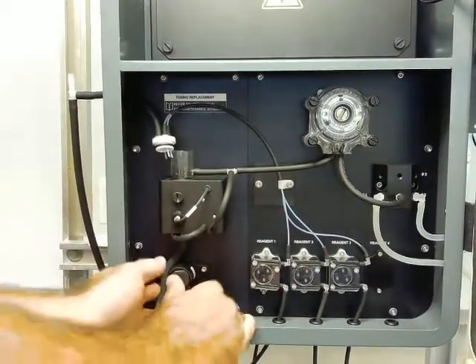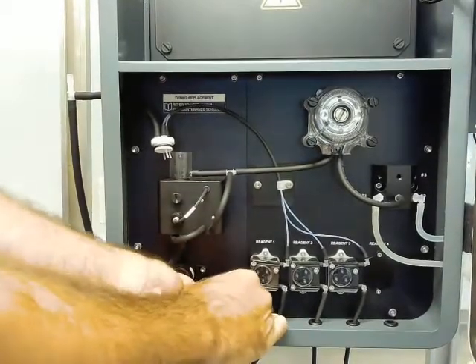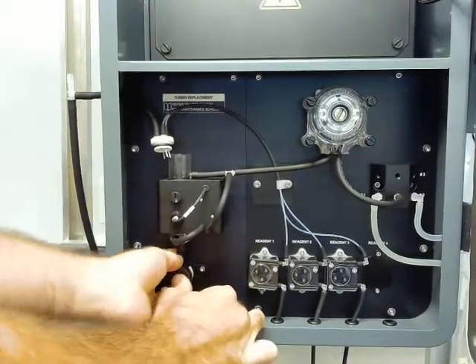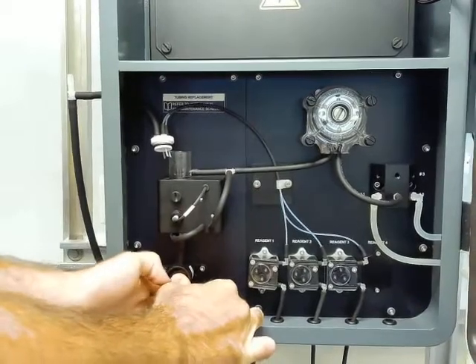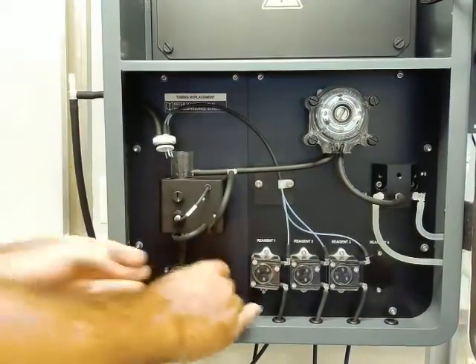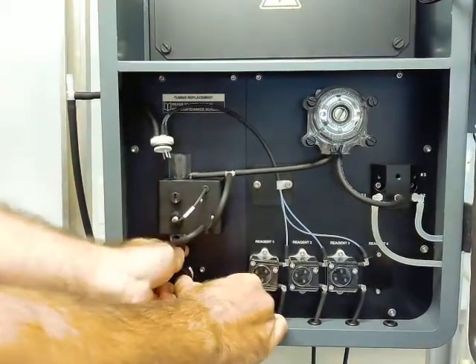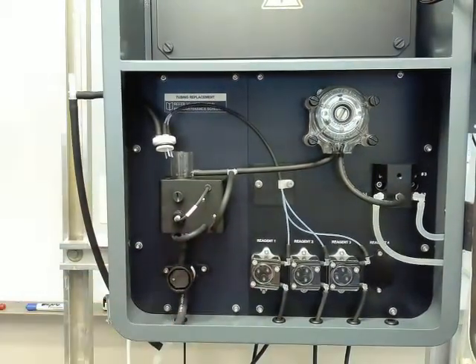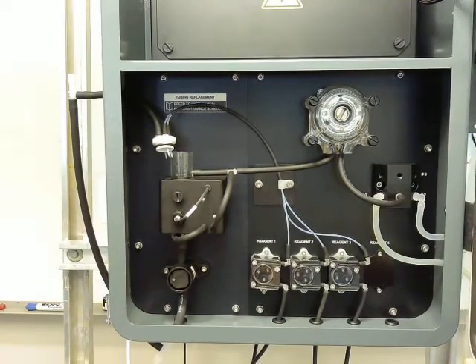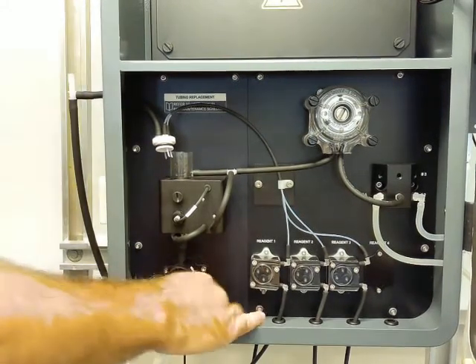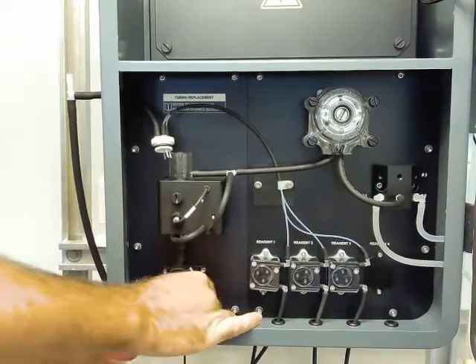So now we got our flow cell back in place. We have to push our tube for our drain back in by manually pressing in the drain valve and then sliding the tube in place. Again, after it's in place, do a little up and down just to make sure that tubing isn't twisted. If it's twisted, it might not pinch closed properly, and then you'll end up with a situation where your flow cell won't retain any of the sample and it will just drain out while you're trying to fill and mix, and obviously end up with bad readings.